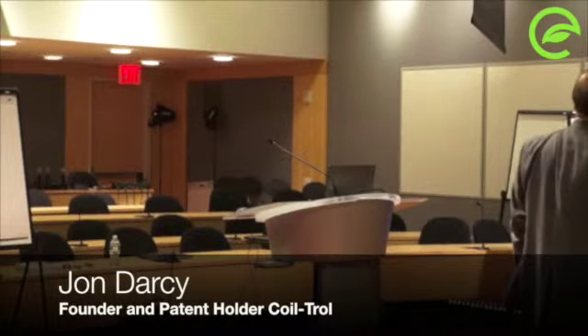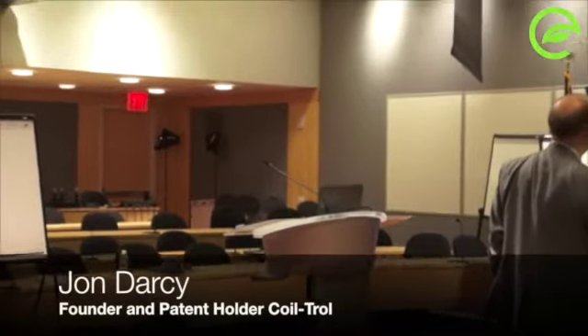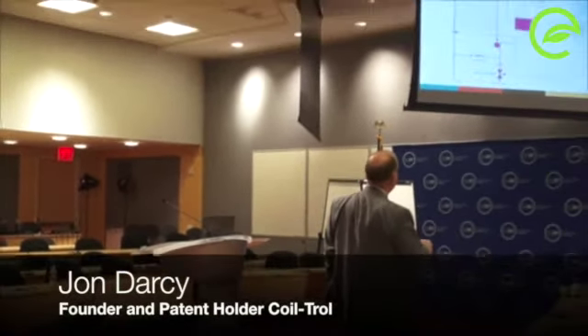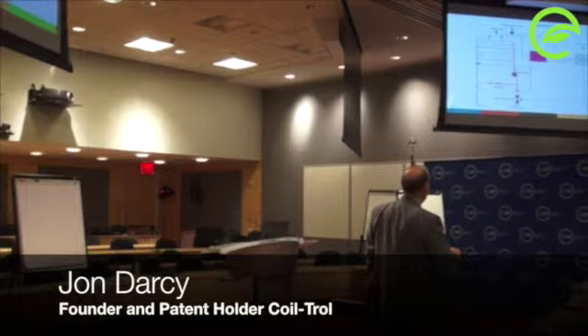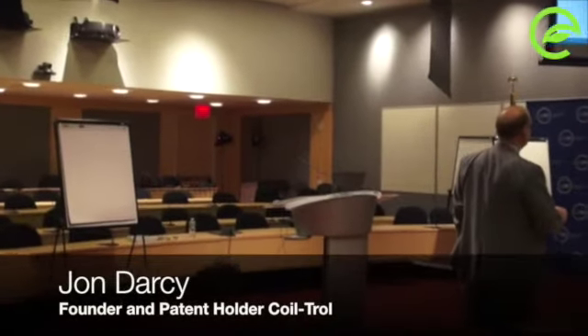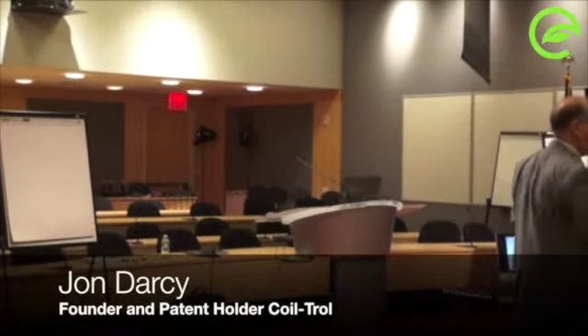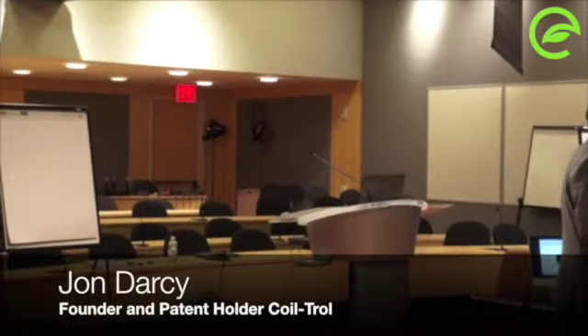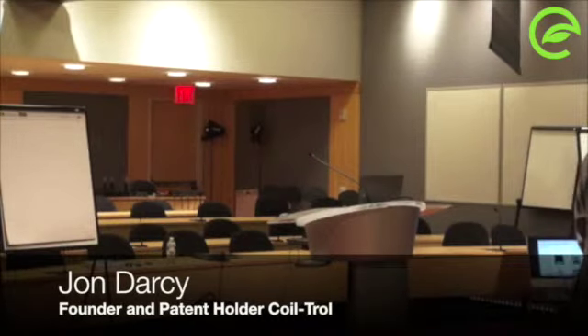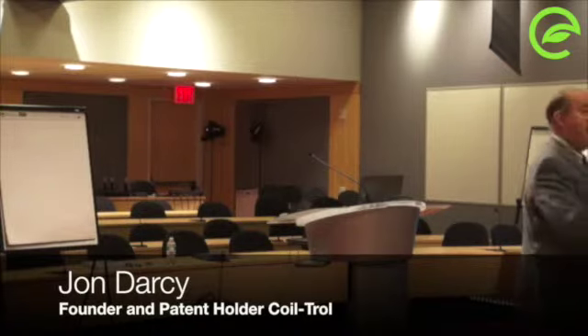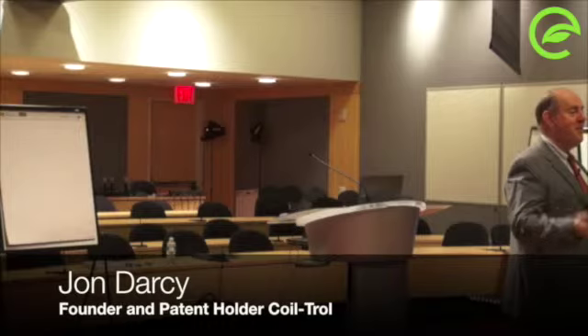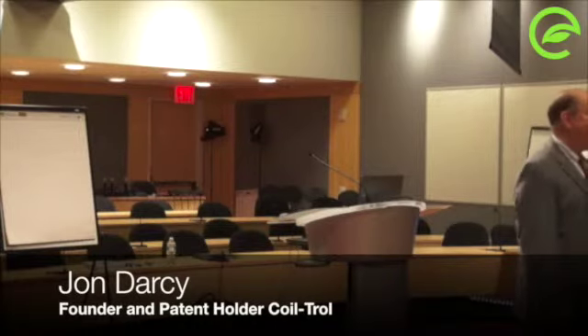So what happens is this pump either goes this way and recirculates, or it returns it, and this is the controller that's already there coming off your building automation system, controlling the discharge air temperature. We're resetting the discharge air temperature while we're still maintaining our temperature and humidity. I'm not doing anything that's different from chill water reset. This is chill water reset.